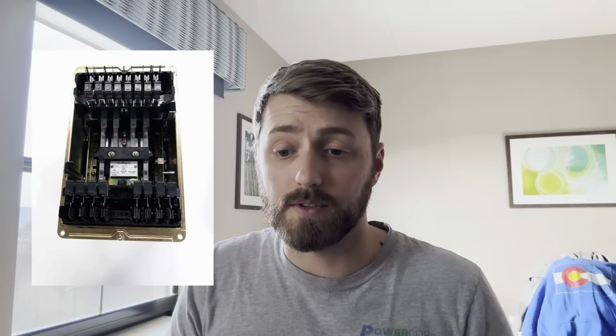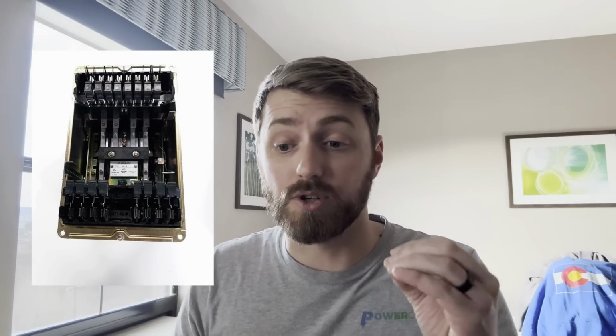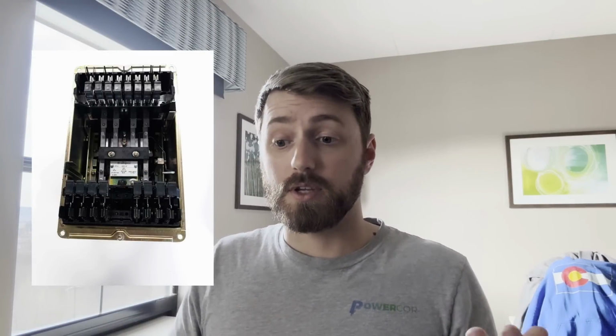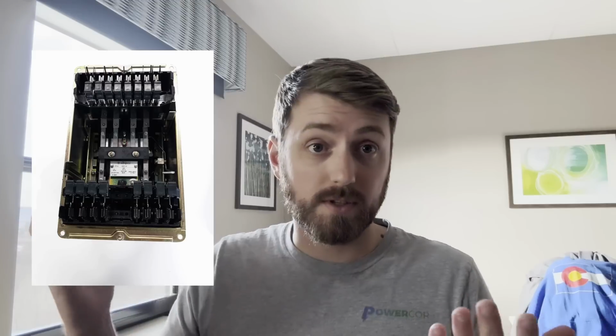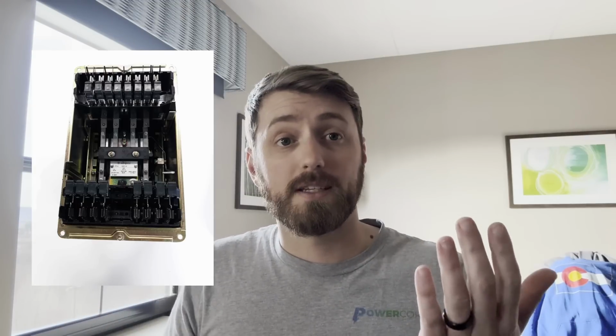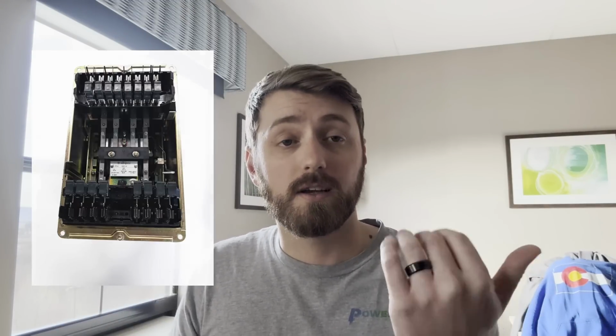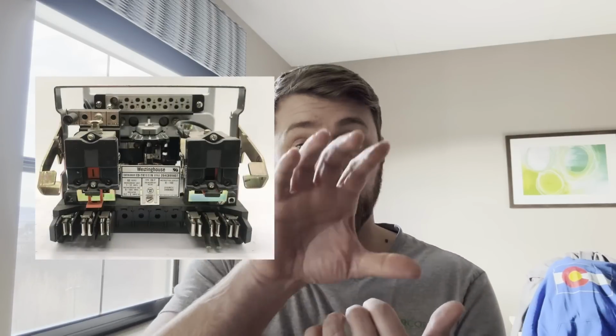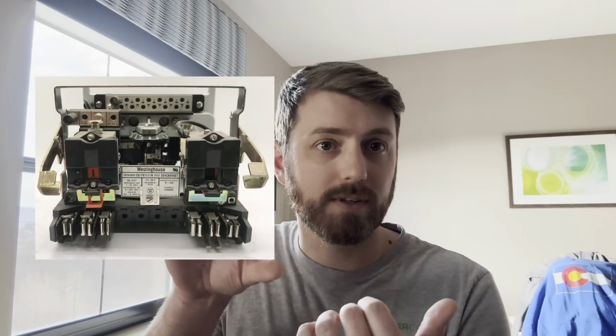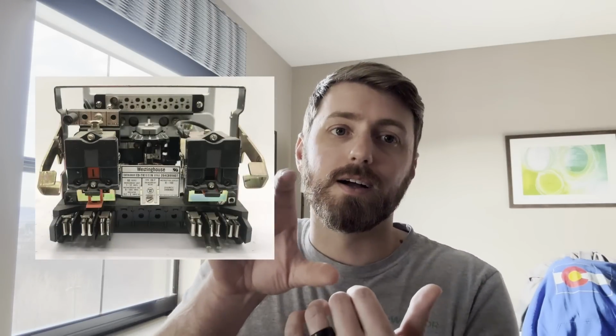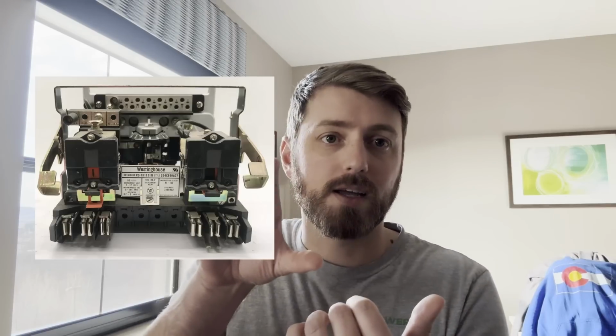All of the relays of this vintage, by the very nature of their construction, have the circuits from the switchgear or from the substation coming up to the bottom of the test switch, and the blades come out the front. So the stationary contacts on the top are physically on the relay, the guts of it, the part that does the protection. That's just how it was built.